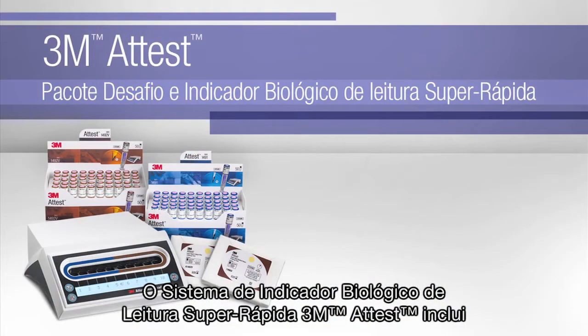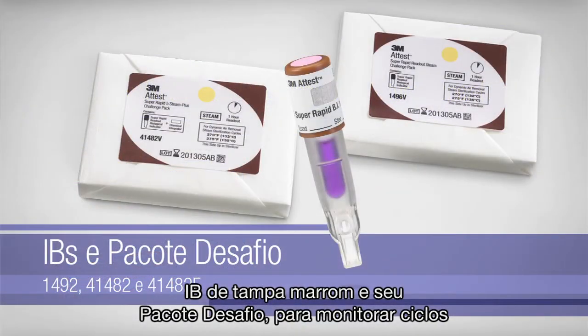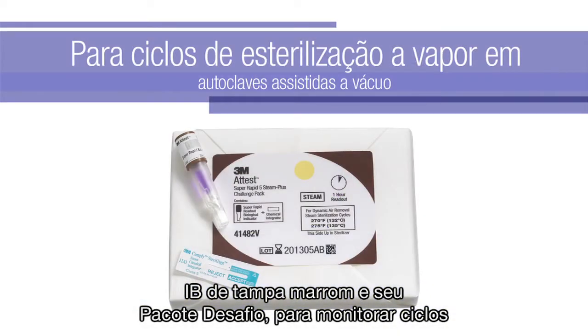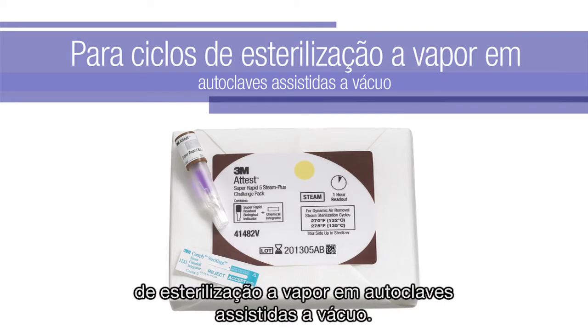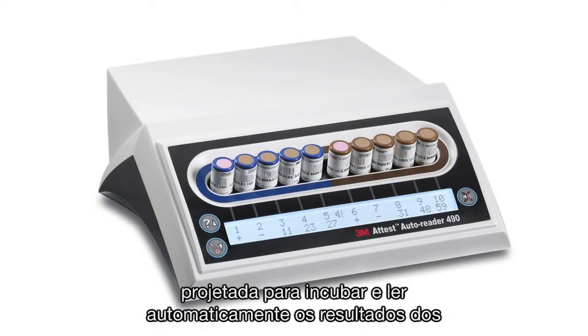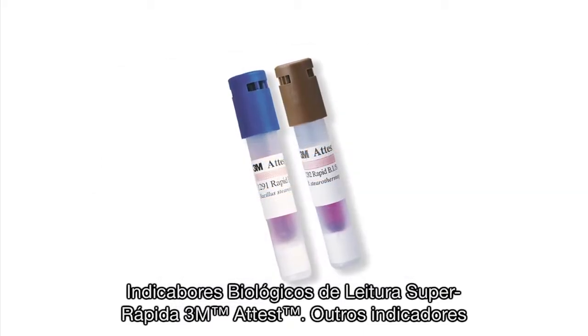The 3M Attest Super Rapid Readout Biological Indicator System includes biological indicators and challenge packs. 1492V Brown Cap BIs and associated challenge packs monitor 270° and 275°F vacuum-assisted steam sterilization cycles. The system also includes the 3M Attest Auto Reader 490, designed to incubate and automatically read the results of 3M Attest Super Rapid Readout BIs. Other biological indicators are not compatible and cannot be used with this auto-reader.